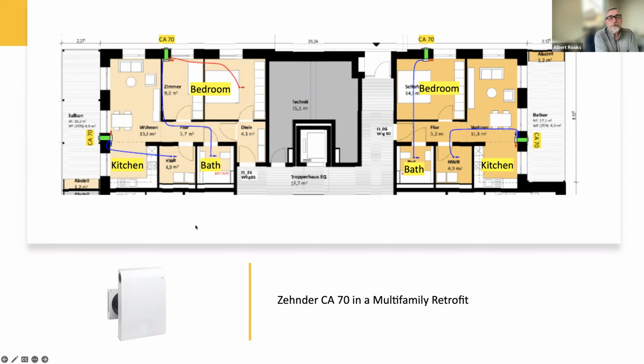And so we look at this floor plan, and over on the right-hand side, we've got a CA70 placed in a kitchen, and it's supplying fresh air to that kitchen area, but it's also got that blue line picking up from that secondary room and pulling exhaust out of that laundry room, for the washing machine and things like that. So it's constantly exhausting there. It could be just sitting there and pulling depressurized air from it, but because of that blue line there, it's probably ducted all the way there.